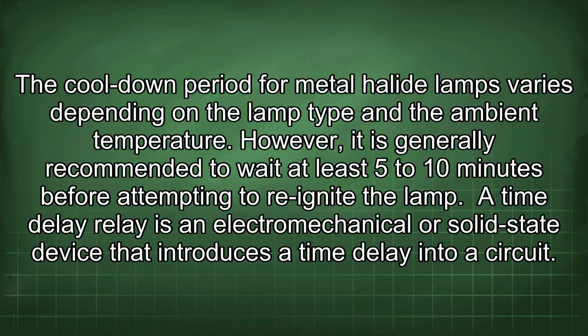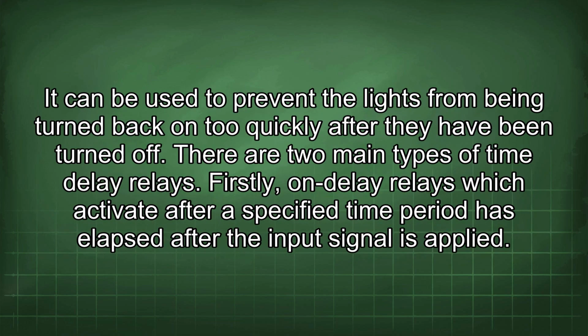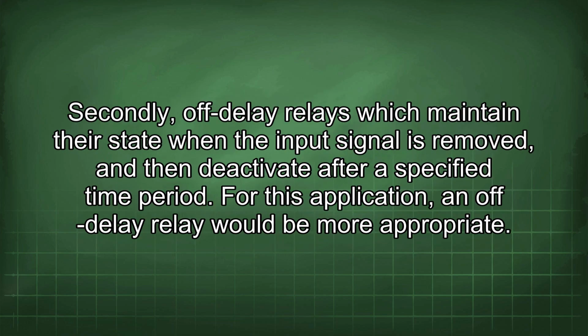A time delay relay is an electromechanical or solid-state device that introduces a time delay into a circuit. It can be used to prevent the lights from being turned back on too quickly after they have been turned off. There are two main types of time delay relays. Firstly, on-delay relays, which activate after a specified time period has elapsed after the input signal is applied. Secondly, off-delay relays, which maintain their state when the input signal is removed, and then deactivate after a specified time period. For this application, an off-delay relay would be more appropriate.